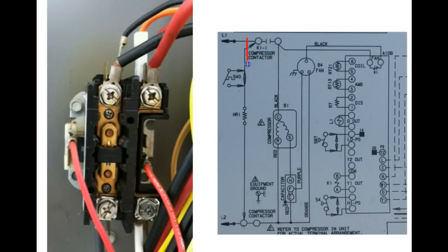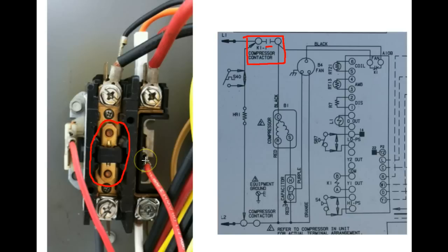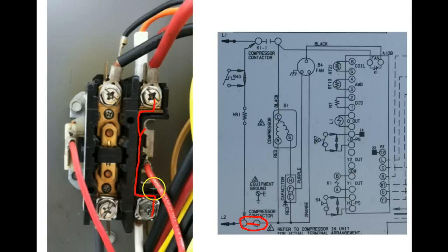Looking at K1-1, the compressor contactor, you can see this shows a break in the electrical path right here. That break is represented by this contact symbol that gets pulled in when the coil is provided with voltage. Then we have the compressor contactor down here, which is just a straight electrical connection represented by a bus bar. This bus bar makes complete contact all the way through. That is how this portion of the contactor is represented on the schematic diagram.